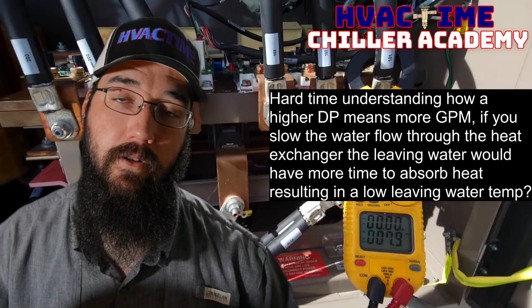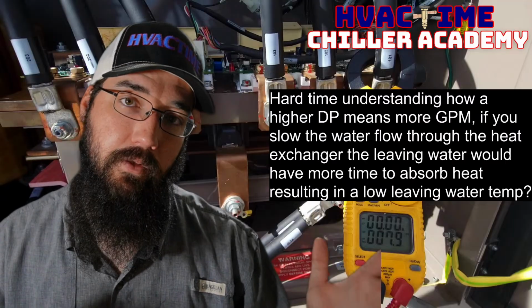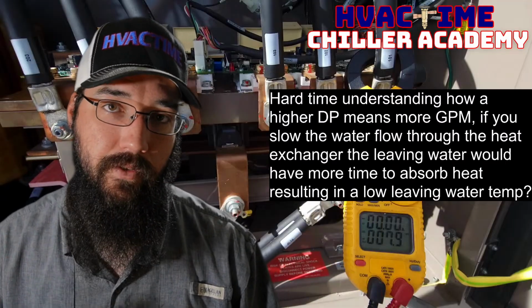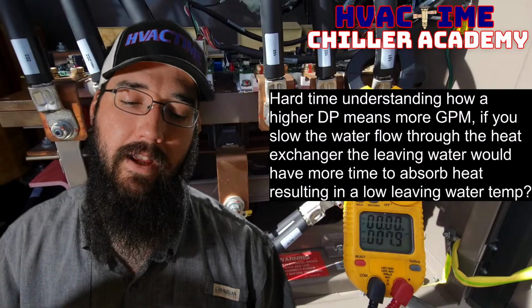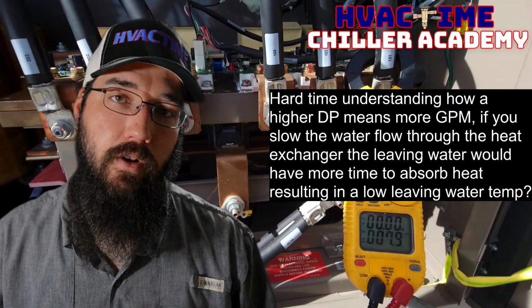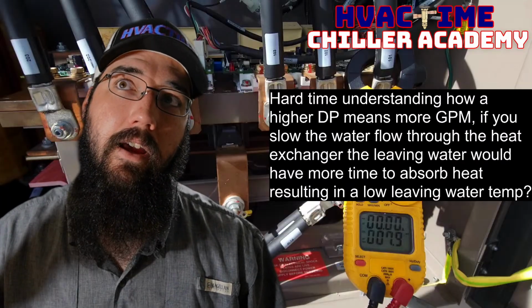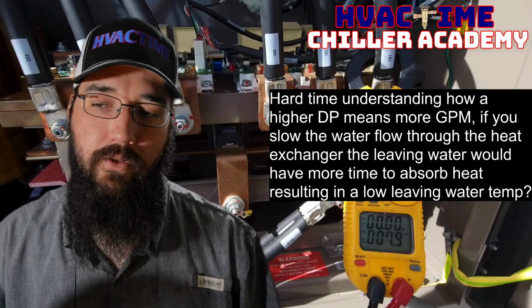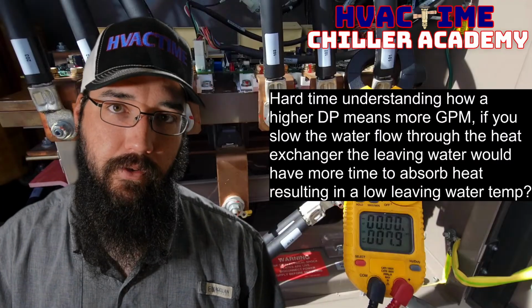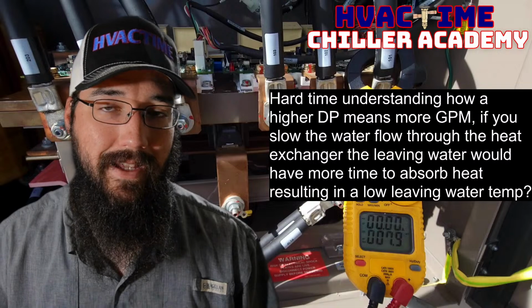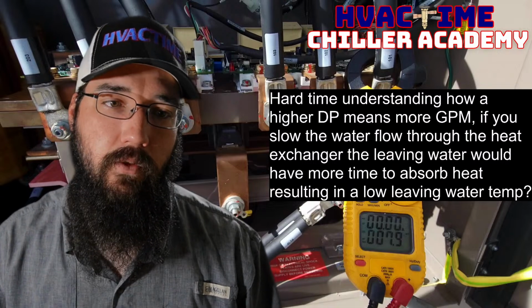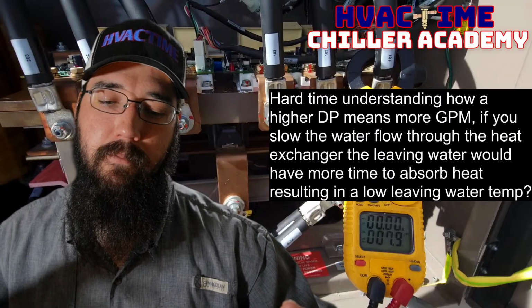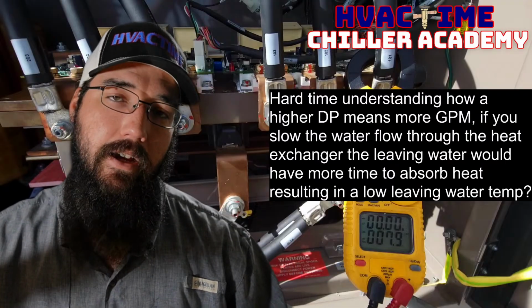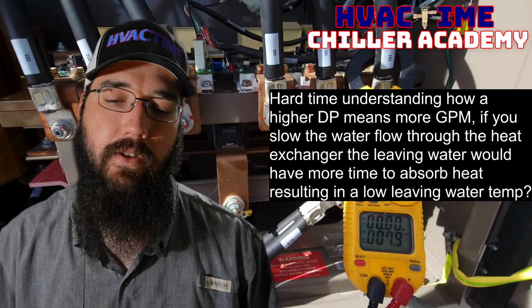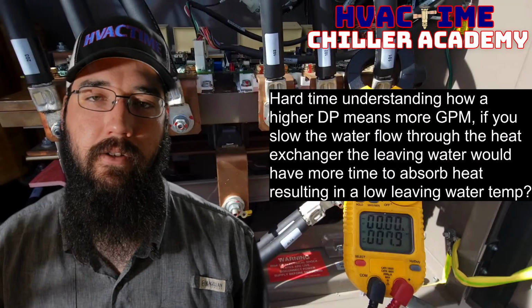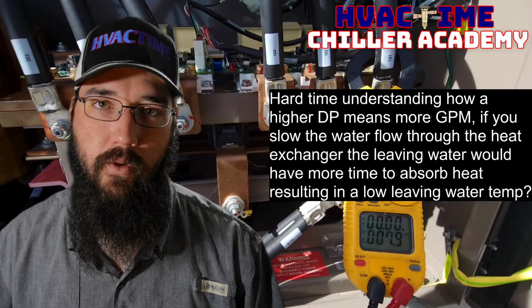which ultimately will force our saturations to drop lower, which gives us a higher approach, the difference between leaving water temperature and refrigerant saturation, specifically evaporator approach in this case. So because we have that higher approach, we're allowing a higher rate of transfer, right? The bigger the gap, the faster it's going to flow from water to refrigerant in terms of heat, just to achieve leaving water set point. So that would be a high GPM flow, which is not good, because then we're just putting way more stress on the machine. That's going to put more stress on our tube bundles, the whole bit.